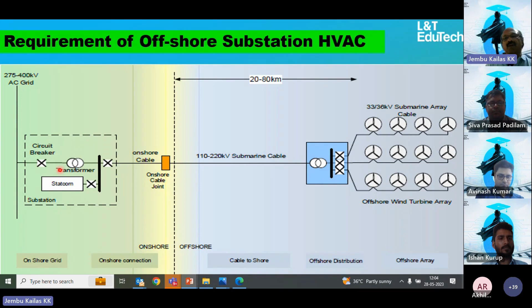If it is more than 80 kilometers, we cannot use AC cable. As I mentioned with the Leh Ladakh case, AC cable cannot go beyond 100 kilometers due to cable reactance and the nature of AC. So beyond 80 kilometers we should use HVDC, connecting all the 33 kV or 36 kV submarine generators.